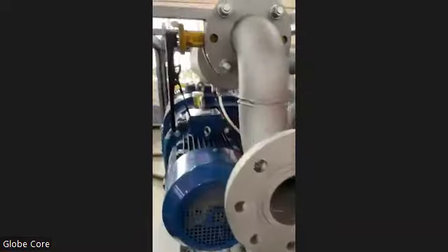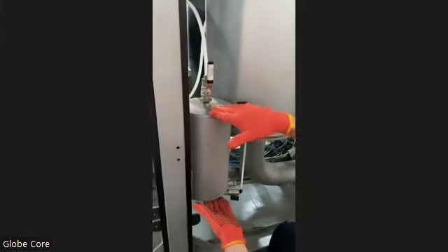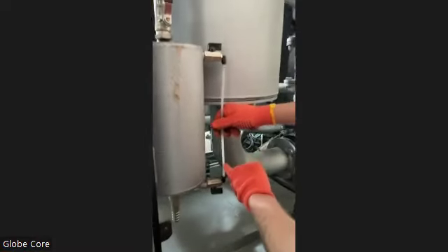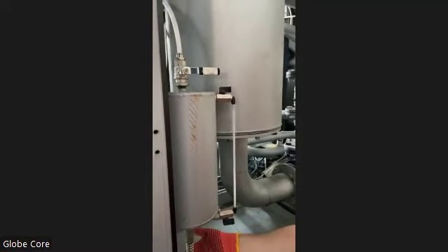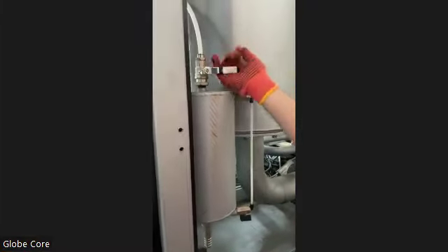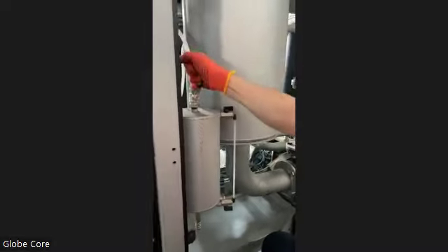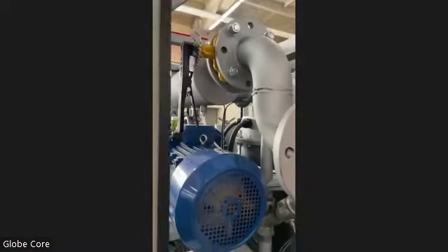By the way, from this point, oil from the oil trap moves to this vessel. And from here, you can drain oil at any moment with no interruption of operation. You can see the level of oil in here, and by cutting off the vessel, you can drain the oil captured by the vacuum system. Then close the draining valve and open it again, and wait until more oil comes in here to drain it again. So this is to remove oil from the oil trap with no interruption of the process.